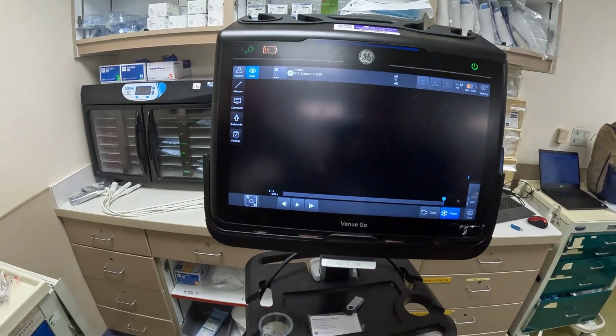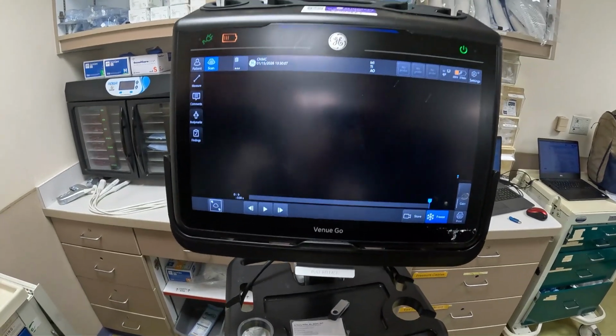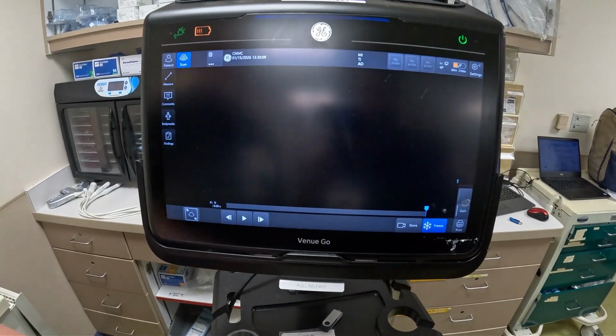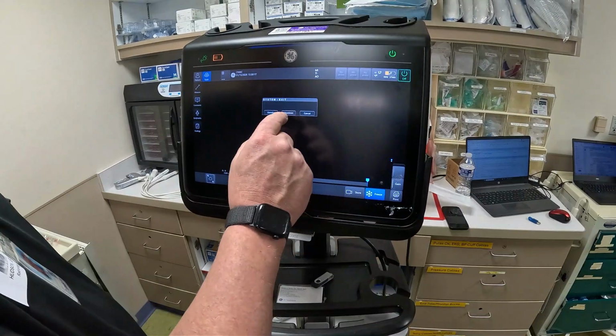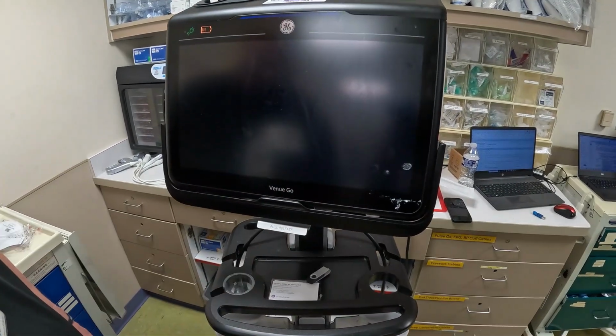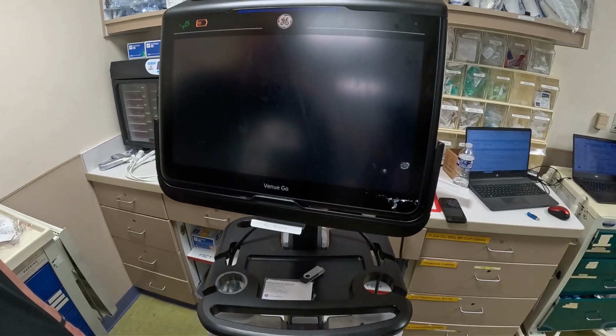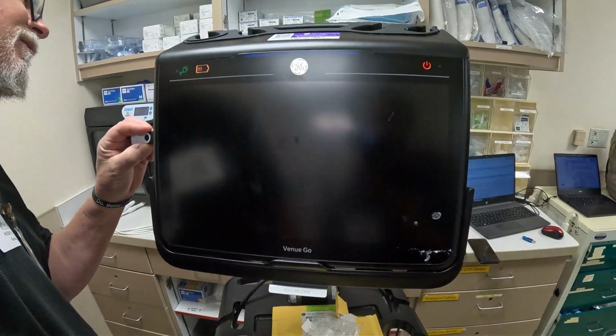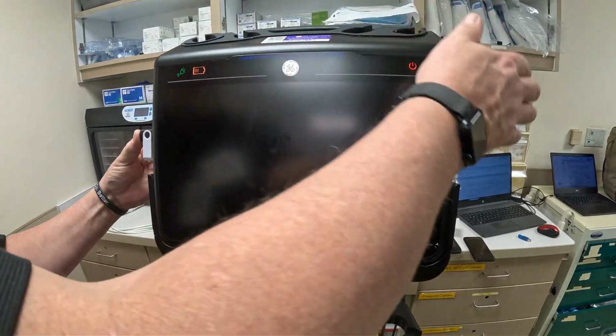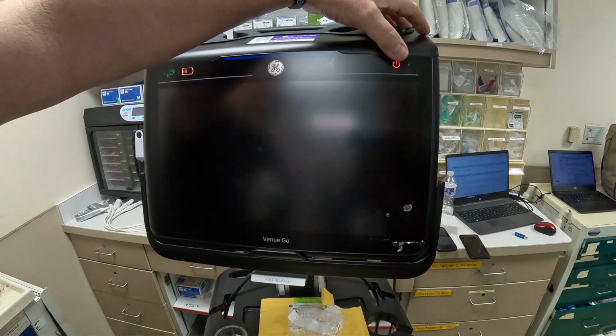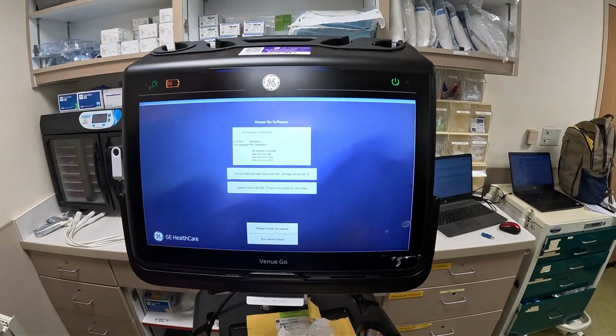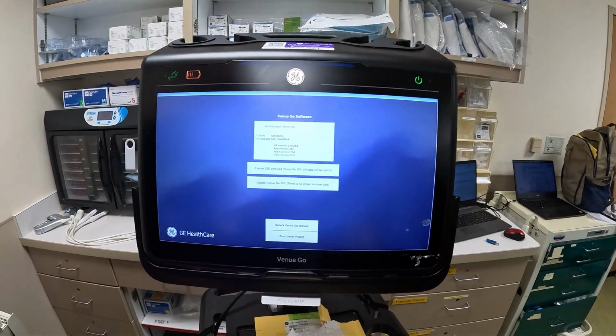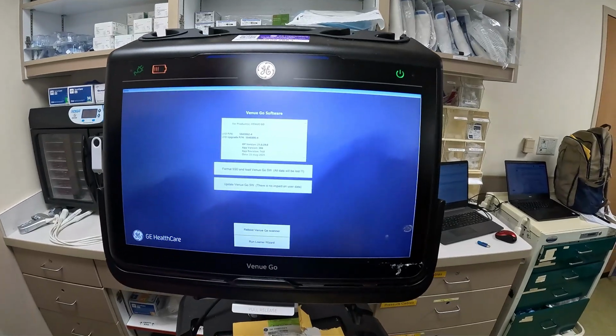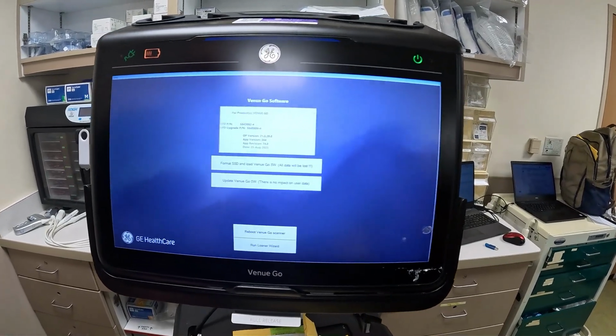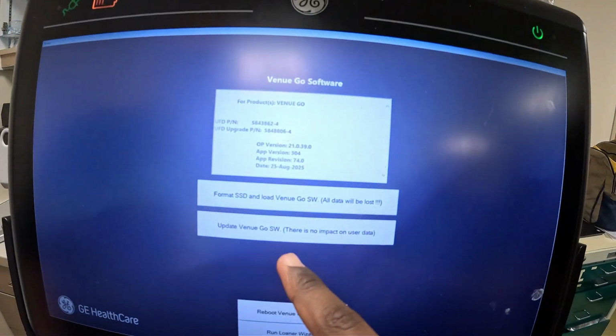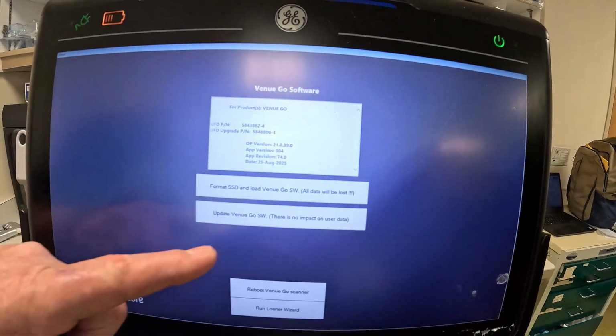Once you're done with the pre-diagnostic test, you'll come back to the start screen of when you turn on the device. So turn off the device now. Shut down. You will get your software USB stick test. Okay. And power back up. And you will see this screen with 4 options. No matter what software you use, there'll always be 4 options, and you always click Update Venue Go software. There is no impact on user data.